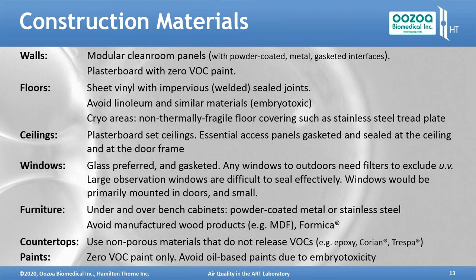For the ceilings, plasterboard set ceilings is typical, and essential access panels, as I said, are gasketed and sealed at the ceiling and at the frame of any door access panel that's in them. Windows, glass is preferred and gasketed. Any windows to the outdoors need filters to exclude UV light. Large observation windows into the lab are difficult to seal effectively. If you really want to have one of those, then probably do it as several smaller windows rather than one huge one. Windows would normally be mounted in doors and kept small, because again, windows are potentially a way of getting through a door if somebody breaks a glass. So again, it should be a security glass.